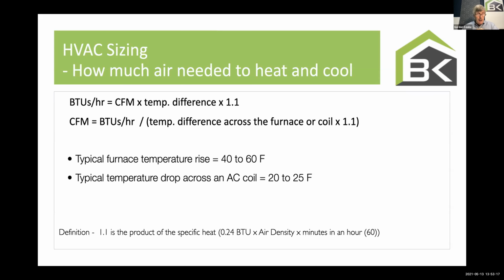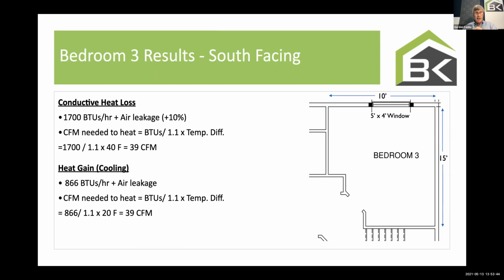How do you know that? The manufacturer will tell you that. They will actually tell you, here's what the recommended heat rise is across my equipment. Same with the air conditioning coil. Notice that the temperature fall across the air conditioning coil is much less. It's about half. It's 20 to 25 degrees. We can only cool air down to roughly 45 to 50 degrees. So we're only cooling it by 25, maybe 30 at the most. So keep that in mind. And we can use that then.